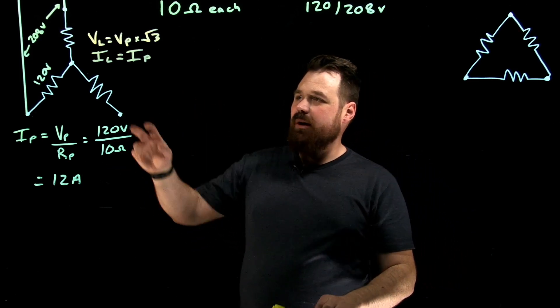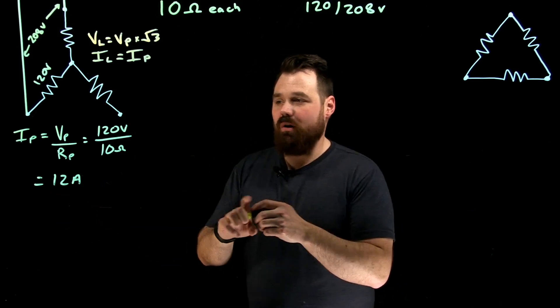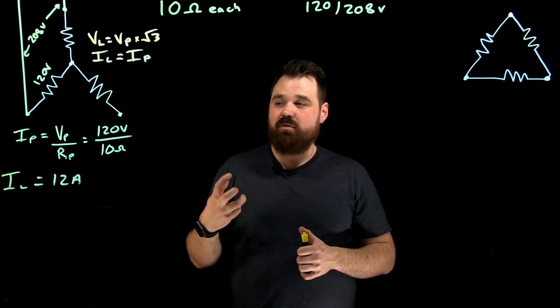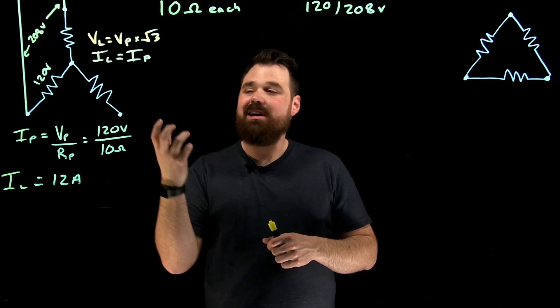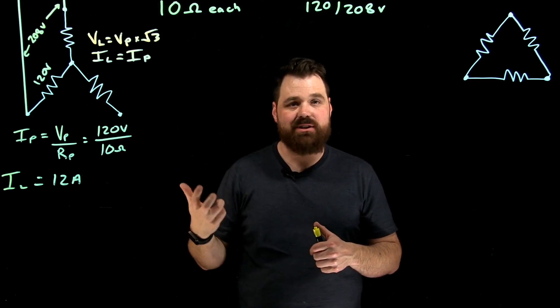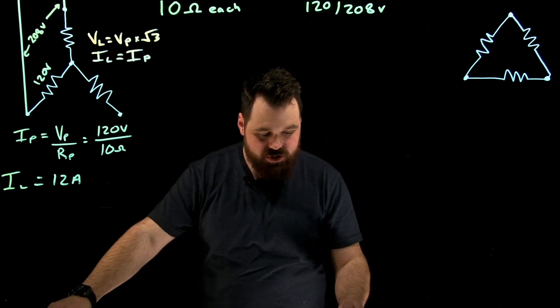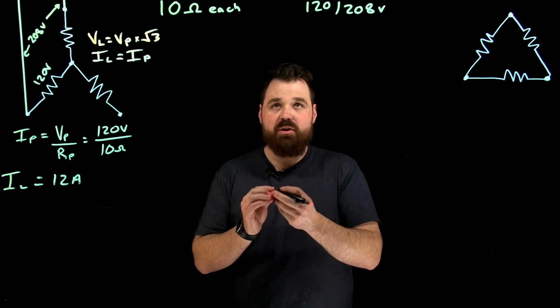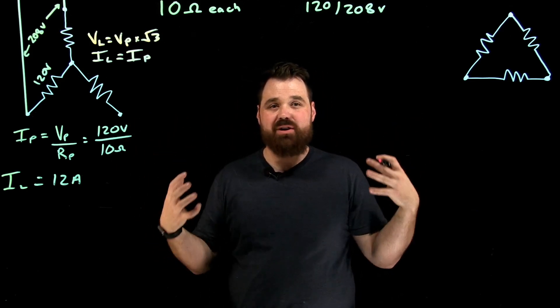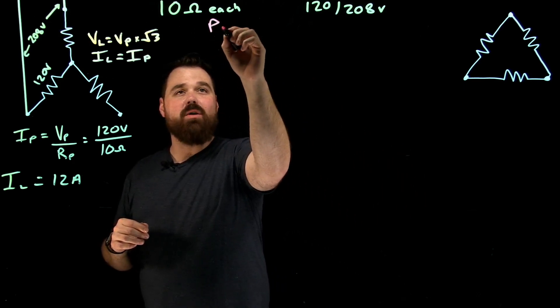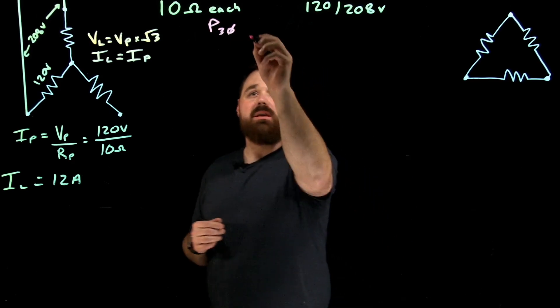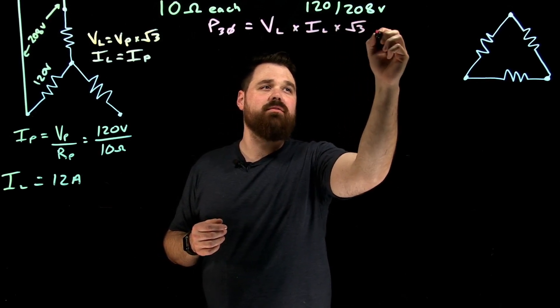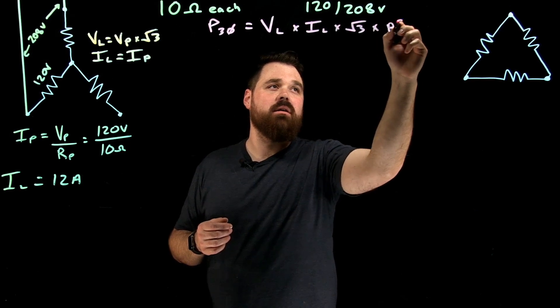So with that being said, if my I line equals my I phase, here where I wrote 12 amps, well yes it's my I phase, but it is also my I line. I just have to make sure when I'm calculating it, I'm using that phase voltage, because that's the actual voltage across the load or across the resistor. Now we're just going to jump into our big formula here. What did we come to talk about? We came to talk about power. So there's one formula that is crucial in three phase when calculating three phase power. And that is that my power, three phase power, is my line voltage times my line current times the square root of three times my power factor.